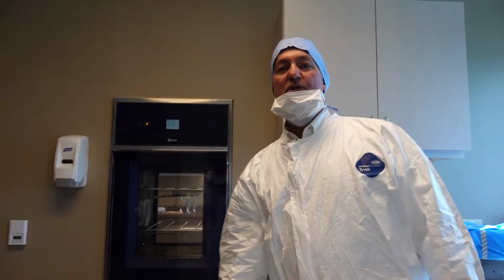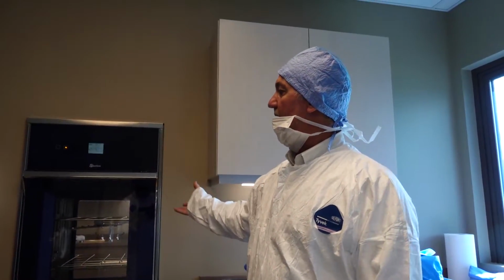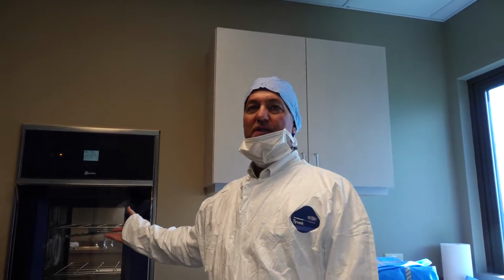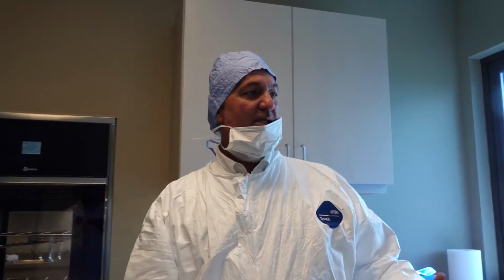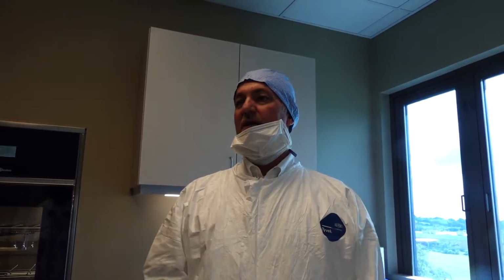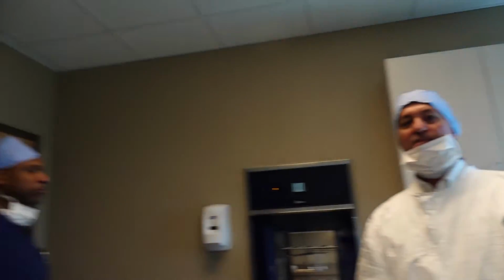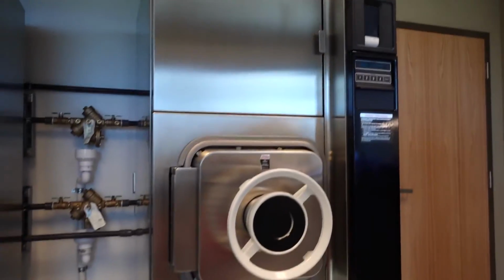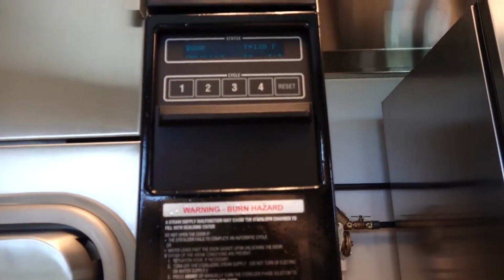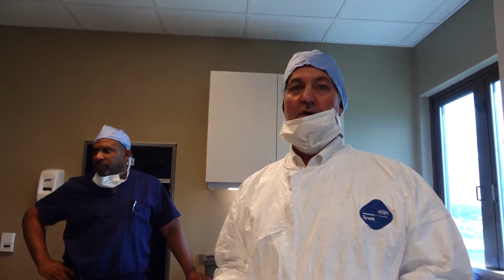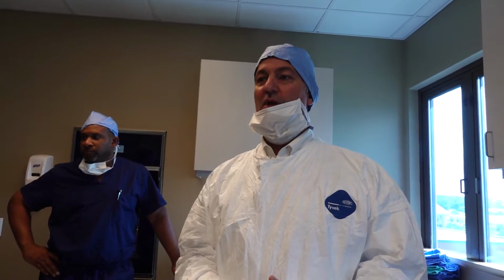So this room is our sterilization room. As I mentioned, on the other side, the decontamination washer gets unloaded on this side, and then as instruments are brought out, the staff takes those instruments, they wrap them prior to being autoclaved and sterilized. The units behind you are two complete autoclaves. They have their own boiler systems built in, water miser systems, water pressure systems. Being in the Virgin Islands, we all know that we have trouble sometimes getting proper water pressure and supplies. So these pieces of equipment have everything built into them.